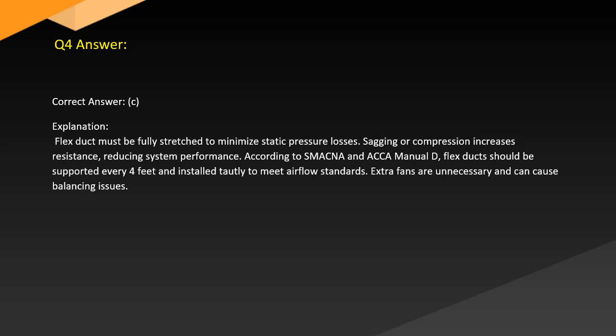Answer. Correct answer, C. Explanation. Flex duct must be fully stretched to minimize static pressure losses. Sagging or compression increases resistance, reducing system performance. According to SMACNA and ACCA manual D, flex duct should be supported every 4 feet and installed tautly to meet airflow standards. Extra fans are unnecessary and can cause balancing issues.